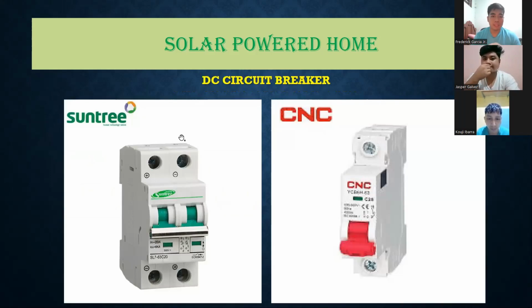Now here we have DC circuit breakers. We use these for the solar panels in case an overload occurs. Here we have a dual gang DC circuit breaker, and here we have a single gang DC circuit breaker. In the dual gang, there's one for the positive and one for the negative, while with the single gang we need two, one for the positive and one for the negative.